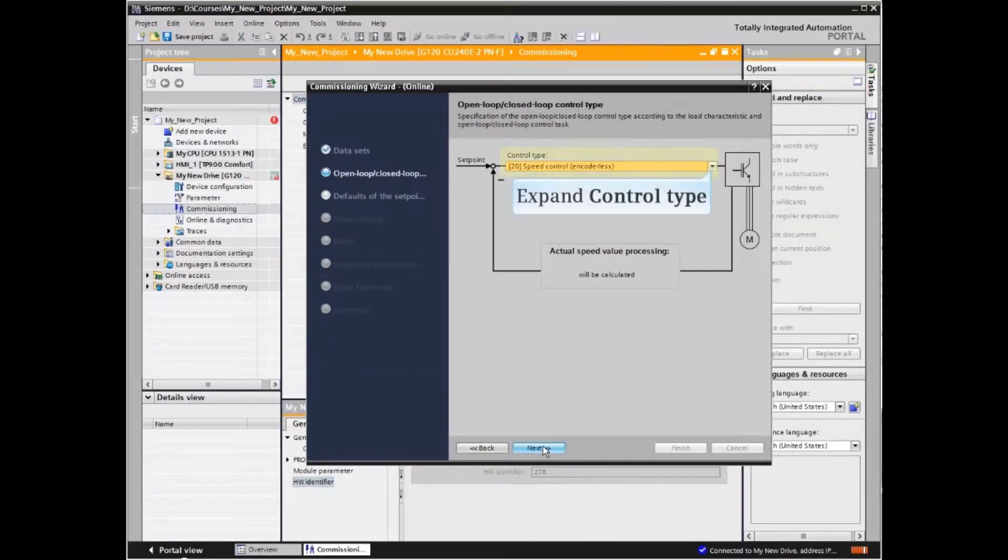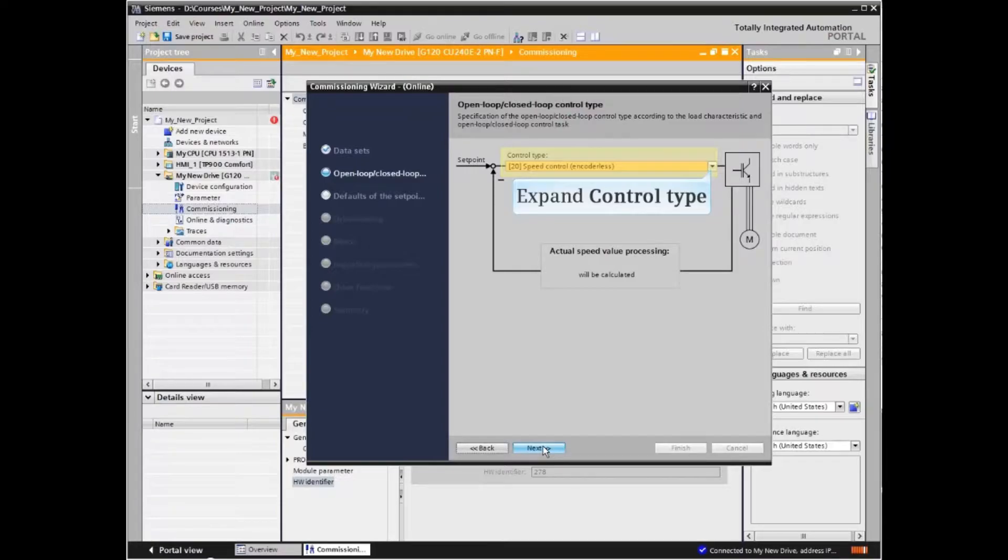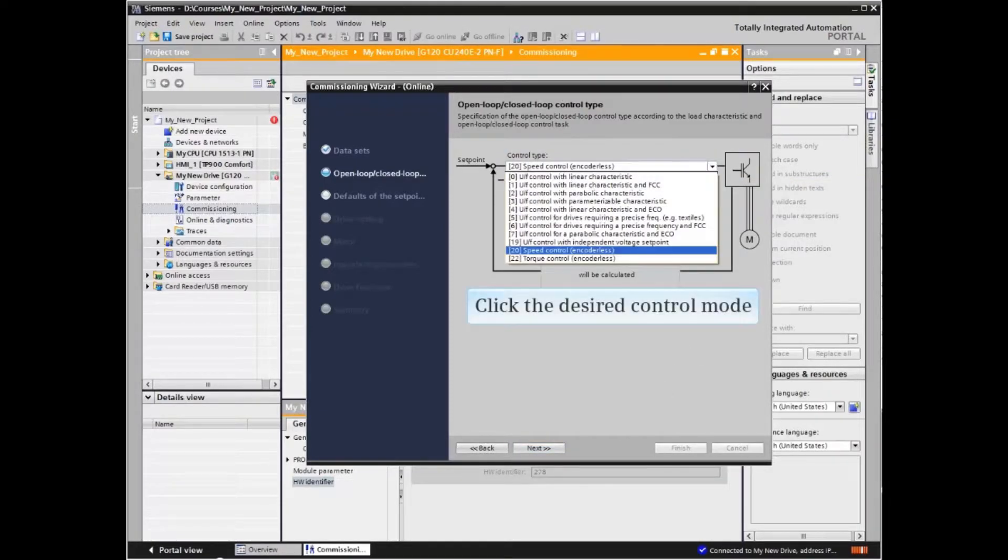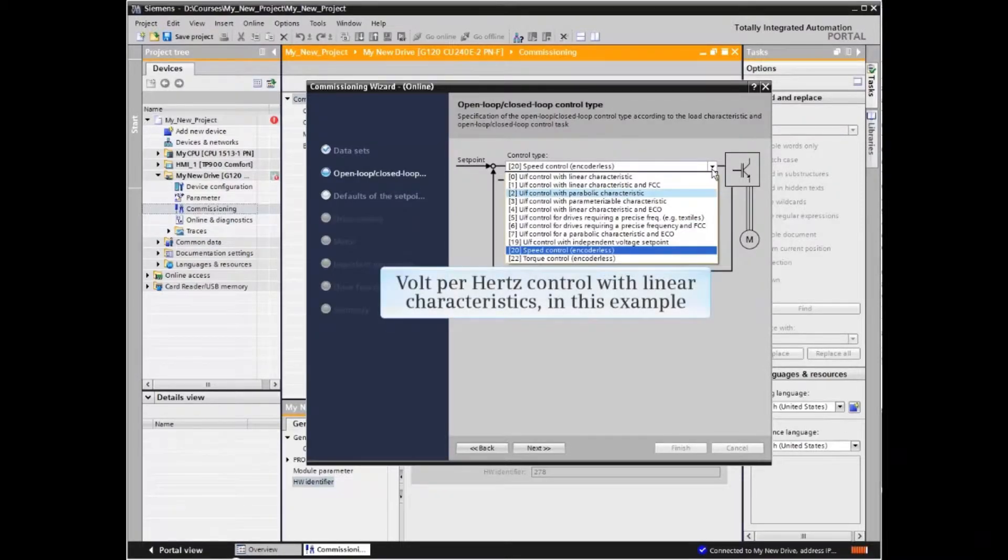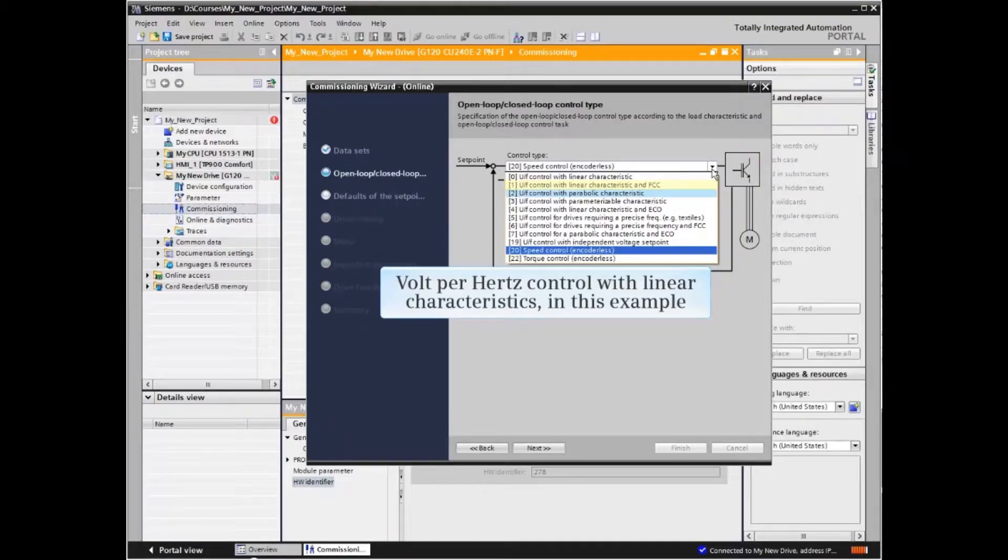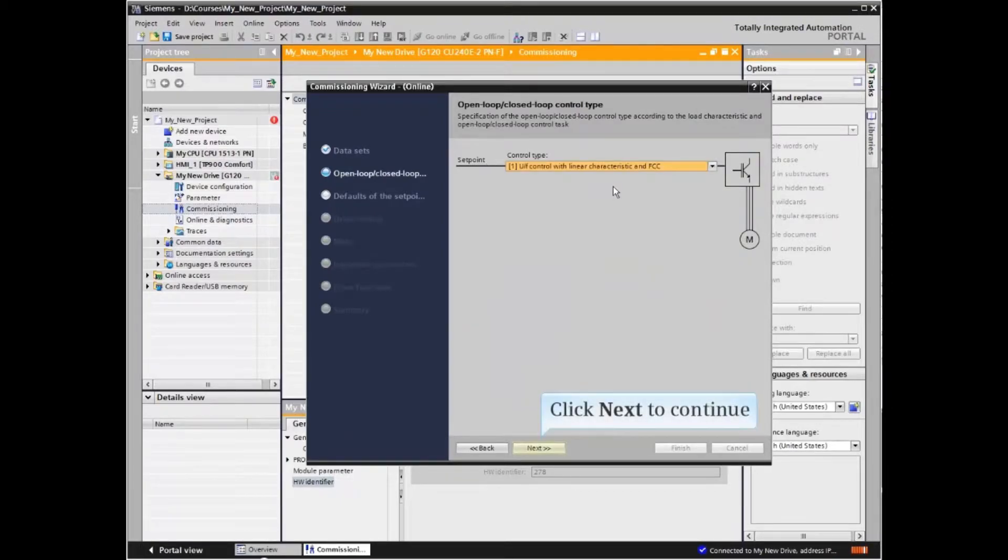Expand the control type menu to choose the open or closed loop control method to match application requirements. Click the control mode desired - volts per hertz control with linear characteristics in this example. Click next to continue.